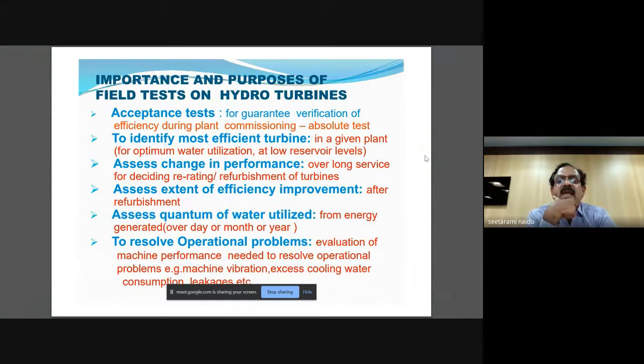But mechanical and electromechanical components like the turbine, draft tube, generator, valves, guide vane, and similar parts of the hydropower plant can be assumed to have a life of only 35 to 40 years. A big review is required after a life of, say, 40 years.